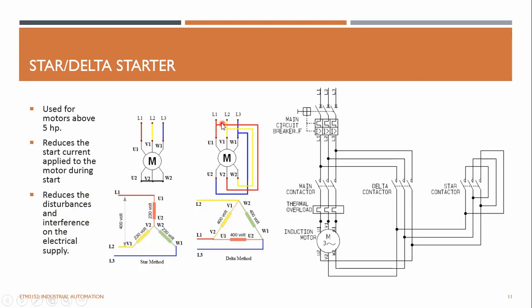And this is how you're going to make it a delta connection. U1 is connected to L1, right? So L1 goes to U1, and U2 goes to W1, and W1 is connected to L3. So U2 goes to W1, and they are connected to L3. And V1 goes to L2, and V2 goes to L1. That's clear. And L2 goes to W2, making it a delta connection.